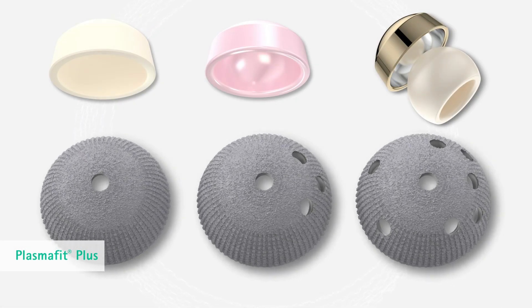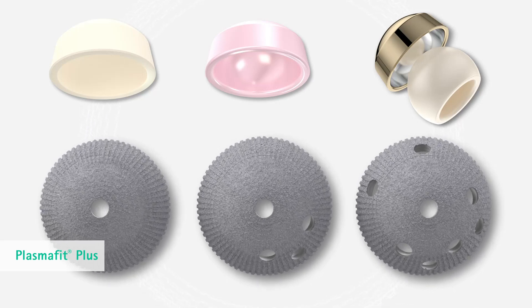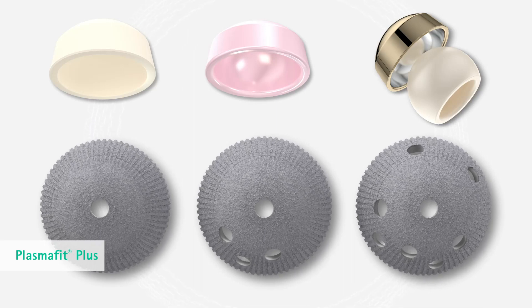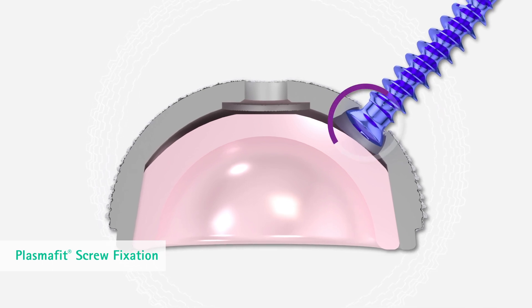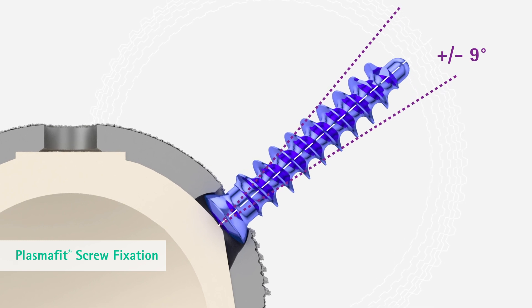PlasmaFit Plus is intended for combined treatment with BIOLOX delta Ceramic, Vitaline or conventional polyethylene, as well as PlasmaFit dual mobility articulating options. The increased wall thickness allows screw holes for optional use of self-cutting fixation screws, which allow a pivoting angle of ±9 degrees.